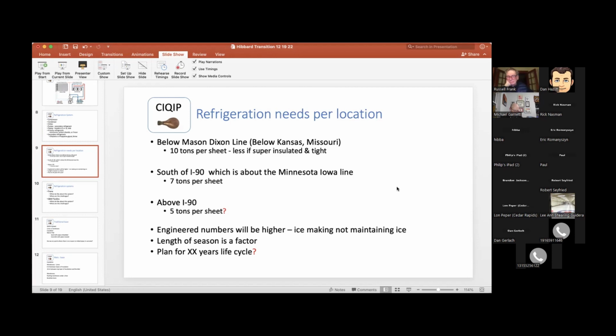The more horsepower you have, the faster you can make ice, but you don't need to make it fast, you need to make it good. To make it good, like anything down south, we use 10 tons per sheet—that gives a little redundancy, and they easily make ice within the week or two they need without wasting money. 7 tons per sheet works from here down into northern New Jersey; below the Mason-Dixon line you go to 10 tons. Above I-90, like Minnesota, upstate New York around the Adirondacks, and Montana, you can get away with 5 tons per sheet.